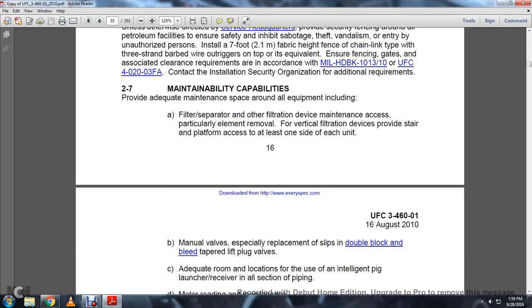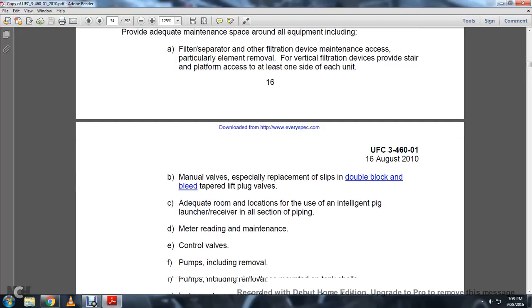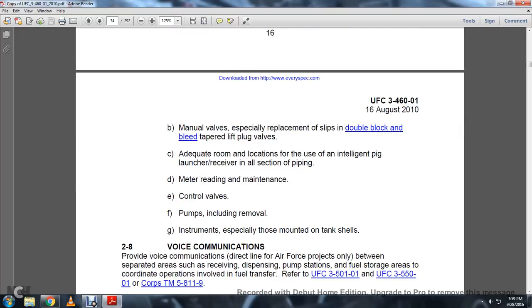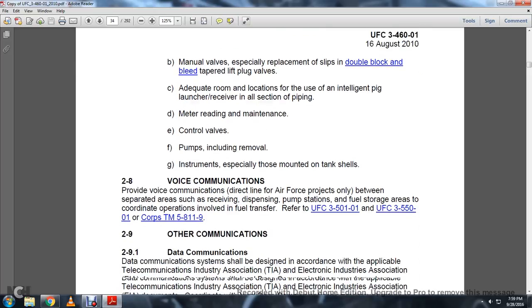2.7 Maintainability. Provide adequate maintenance space around all equipment, including filter separators and other filtration devices. Maintain access for particular element removal; for vertical filtration devices, provide a stair and platform access to at least one side of each unit. Manual valves, especially replacement of slips of double block and bleed, tapered, lift plug valves. Provide adequate room for locations used for the intelligent pig launcher receivers in all sections of piping. Allow meter reading and maintenance of control valves, pumps, including removal of instruments, especially those mounted on tank shells.